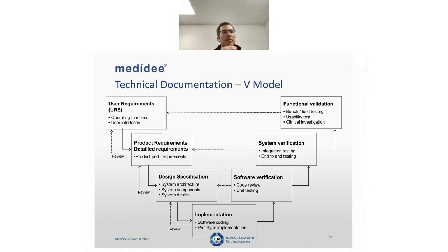This model can be implemented in multiple ways. It's suitable for agile methods because you can make short cycles, but at the end, you always need to be able to show this kind of logic, starting with the user requirement and going through the whole life cycle all the way down to the functional validation. This is the expectation now when you come with your technical documentation. The notified body will look at your documentation and say, okay, let's start with the user requirement, and we go all the way along. Keep in mind also that there is an essential process, which is the risk management process.